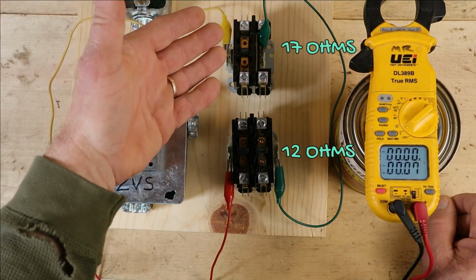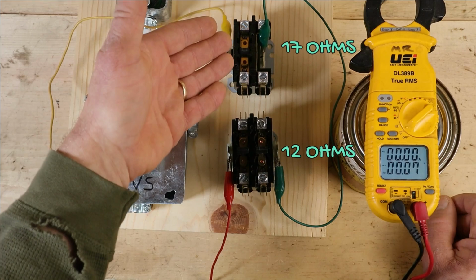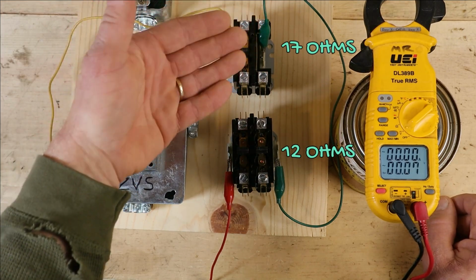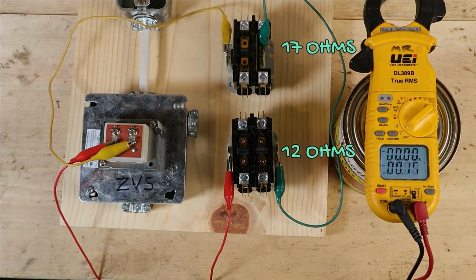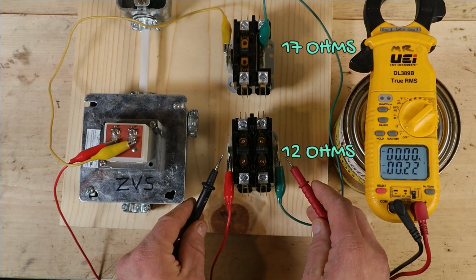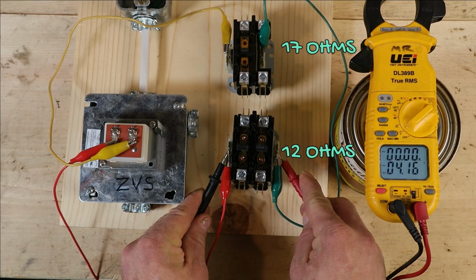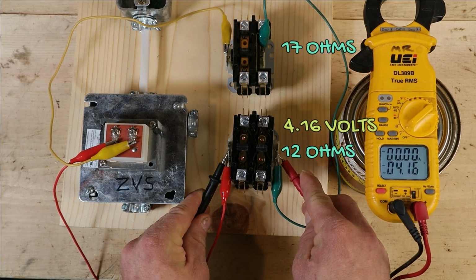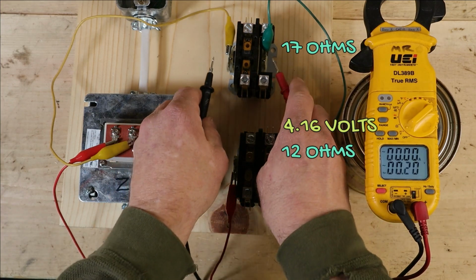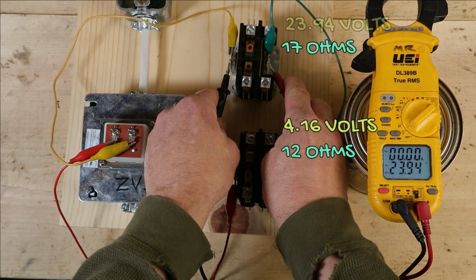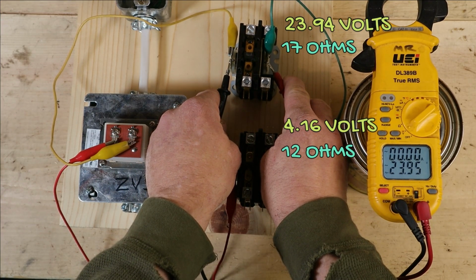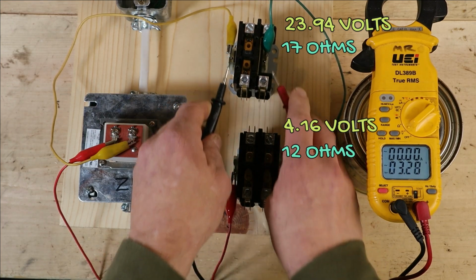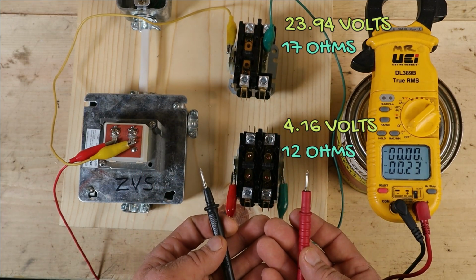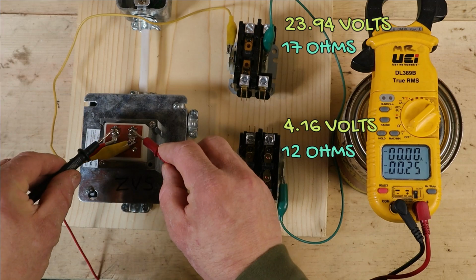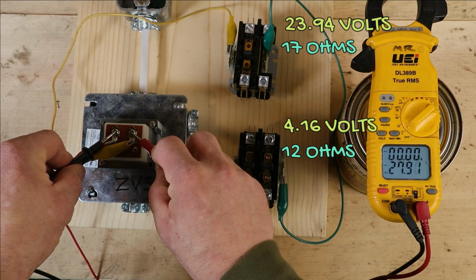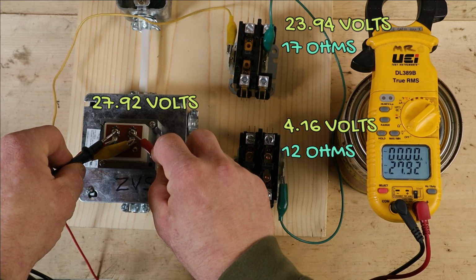Now, as you can see, our contactor with the higher resistance value actually worked. It pulled the contactor in. Let's take a voltage test across our first contactor, and you can see we're only reading 4 volts there. If we go to the other coil and measure both sides, we're reading about 24. So 24 here, 4 here, that's about 28 volts total, which is what we should be reading off our transformer. And there we go, 27.9.